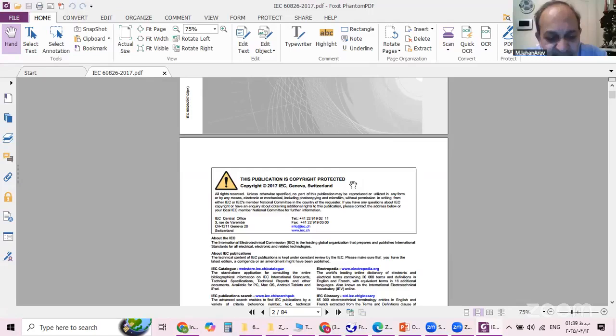Yes, I will explain. Mr. Sultan, you know that not all of the failures are because of wind load, because wind load is one case, and we also have transverse loads. Transverse loads come from the high deviation angle of the transmission lines. These are because of tension of the cable, and it can happen during heavy ice, or during wind and ice together.